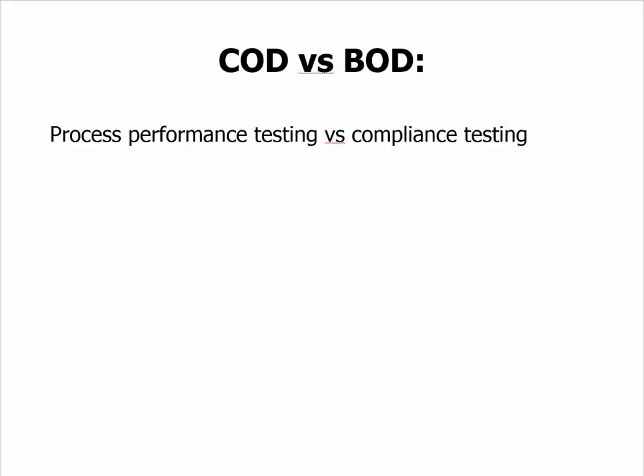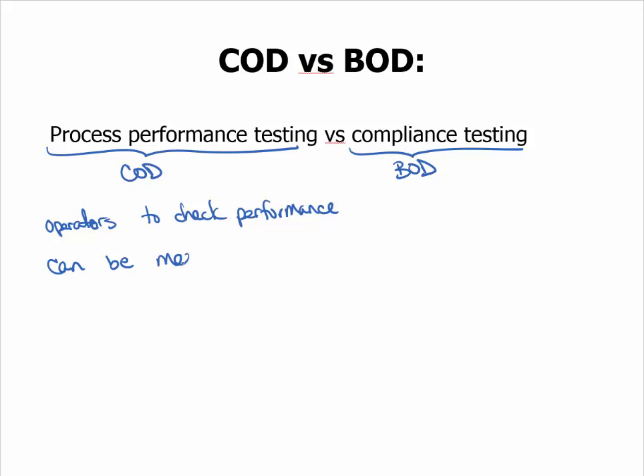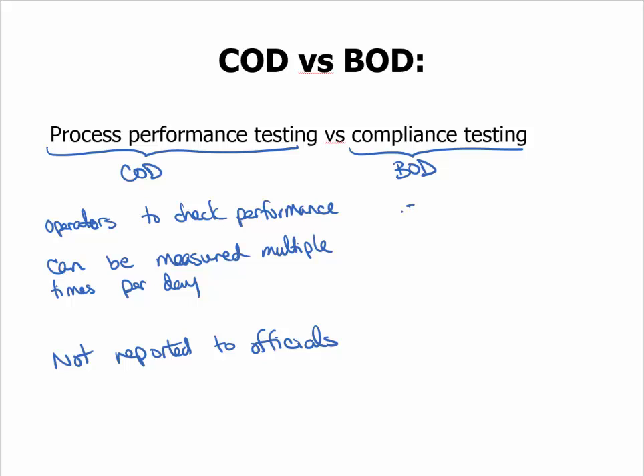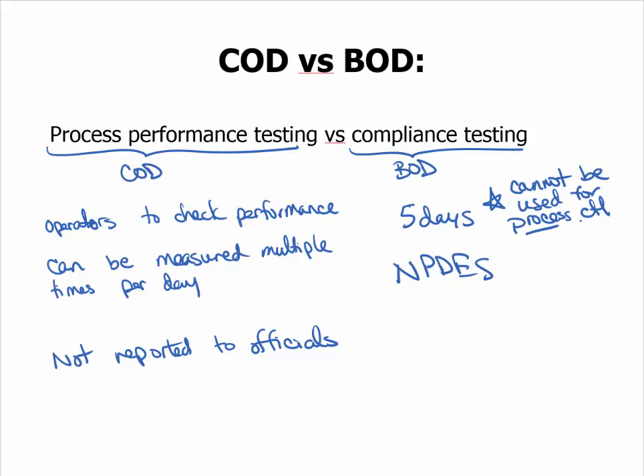There is a learning objective that asks you to compare COD versus BOD. COD is used for process performance testing and BOD is used for compliance testing. Process performance testing is utilized by operators to check performance — it can be measured multiple times a day and is not reported to officials. BOD is measured over five days and is required by the NPDES permit. Because it takes five days, it is not useful for process control, since operators need to respond to mistakes within the process more often than every five days. The COD test, in contrast, takes 2.5 hours.